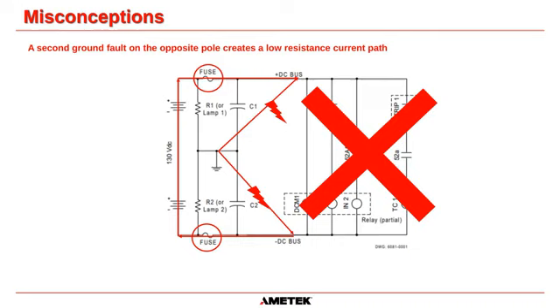I've seen many issues when a Bender is used on a UPS system, or a high frequency charger system where the DC is being created by some form of PWM, or there is reflected PWM from the inverter of the system. So I don't recommend using the Bender or any kind of installation monitoring device that sends a signal while the system is in normal operation. I do like the Megger because that's a test device that you use to try and find the fault, and it's not consistently on the system. But the ones that are used on a charger, I just personally, I don't like them. But once again, that's personal. I'm sure Bender and all the other manufacturers will have a completely different viewpoint, and will say that they work absolutely fine.